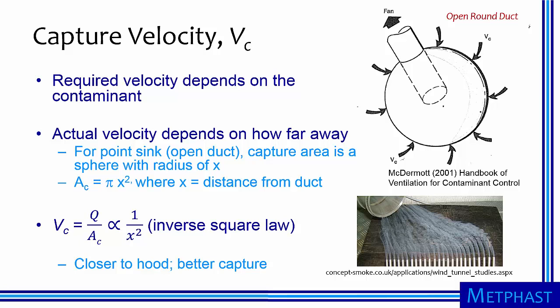The required capture velocity to attain good effectiveness with a capturing hood depends on the contaminant. Dusts require higher velocities than fumes and gases. The actual capture velocity at the source depends on how far away the hood is. For an open round duct, we can model capture area as a sphere with a radius x, where x is the distance from the duct.